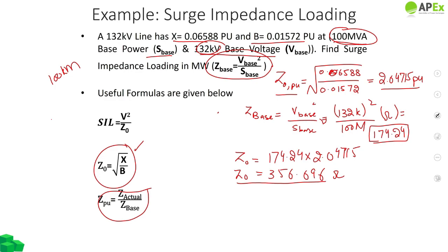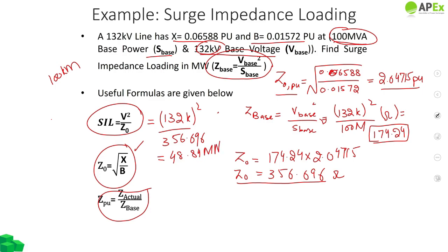We put the values into the surge impedance loading formula, with V as 132 kV and Z naught as 356.696. Doing the math, 132k squared divided by 356.696 equals 48.84 megawatts. So the surge impedance loading of this line is 48.84 megawatts.